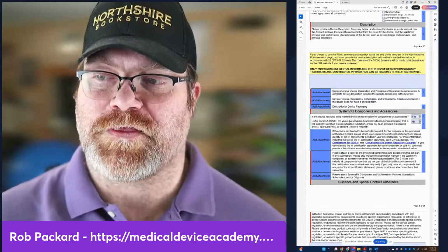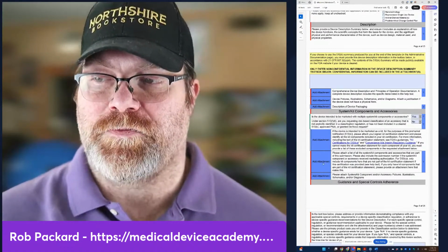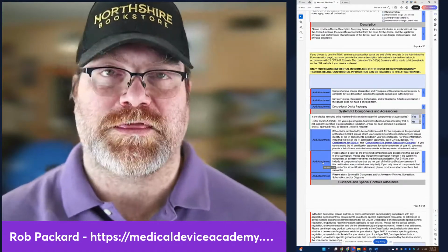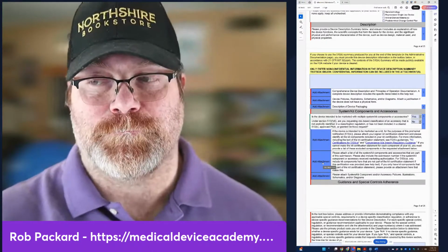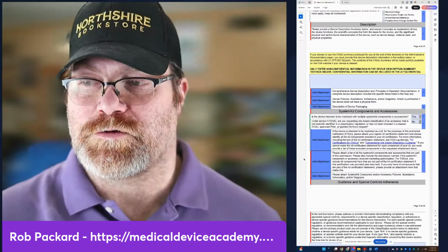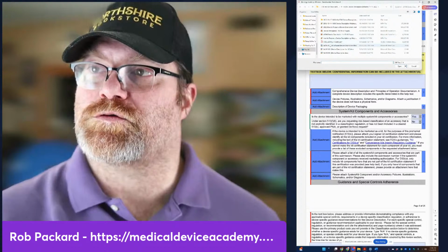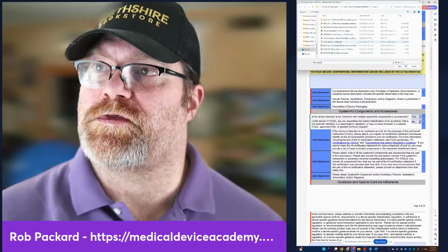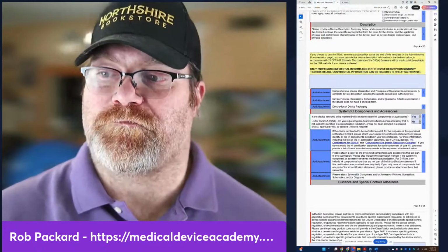It's gray on the left hand side, which says it's optional. The other sections are not. They're required. So this one here, I have to attach a list of my components and accessories. Well, do I need it both in the attached device description, or can I just put it here? I can just put it here. So that would be okay. So I would just attach something, and then it's going to pull up a little box where I can attach different things from my templates or a new Word document that I've created.